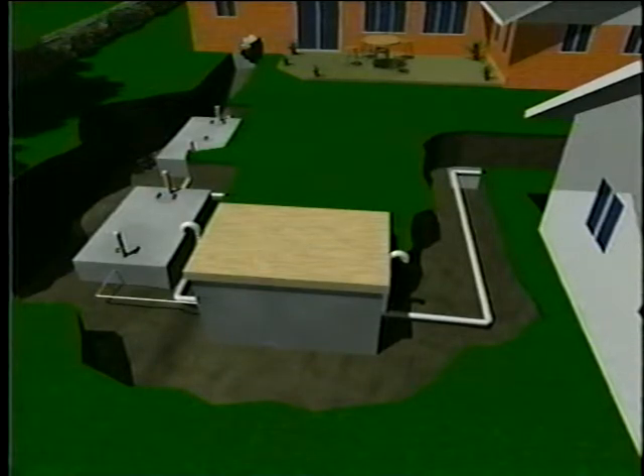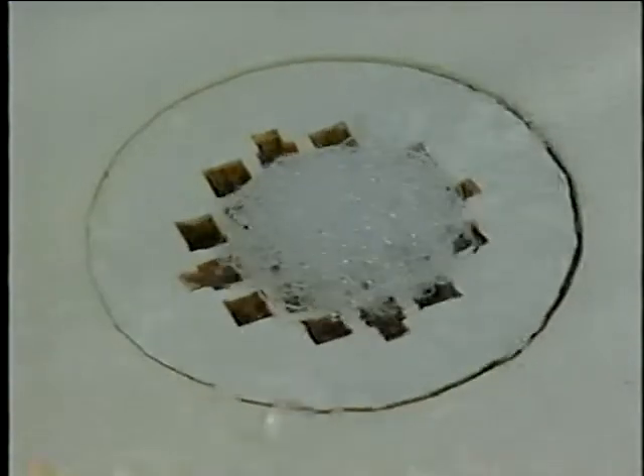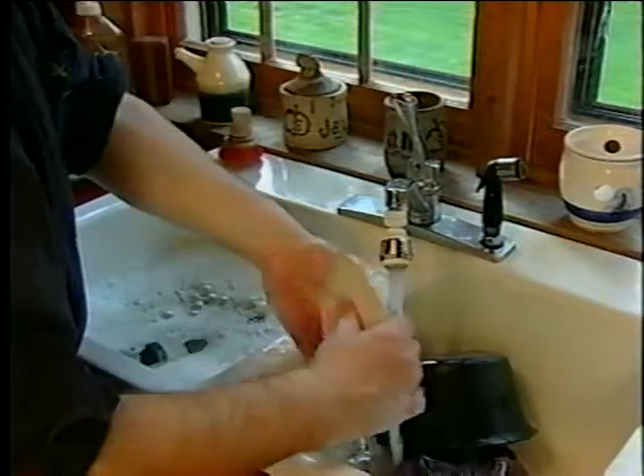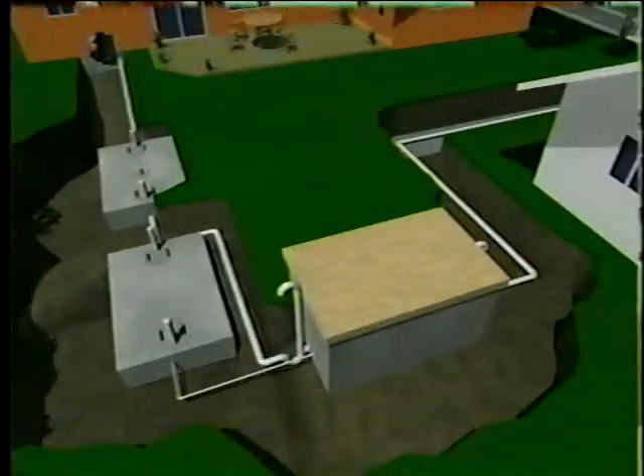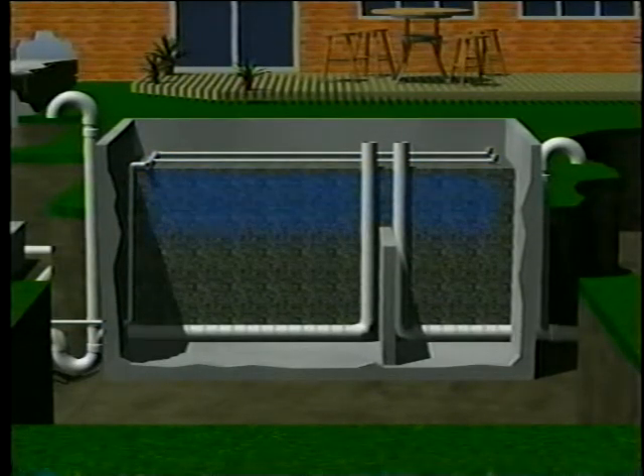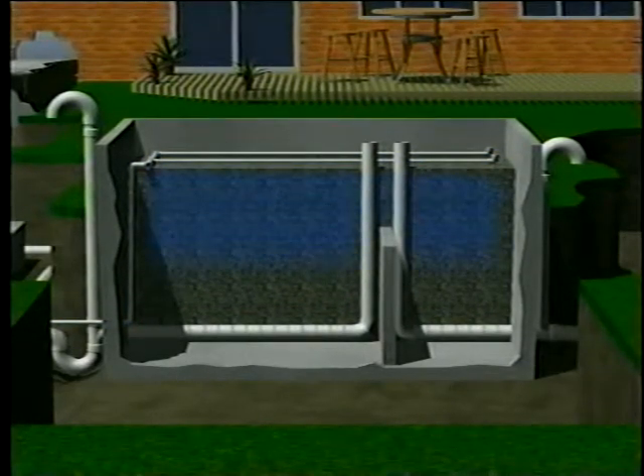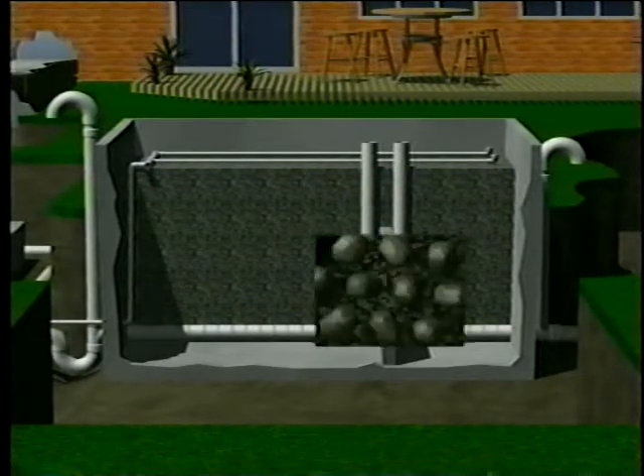During a 24-hour period, the amount of wastewater entering the septic system fluctuates. Peak flow periods are typically in the mornings, evenings, and weekends when families are taking showers, doing laundry, and washing dishes. At night when people are sleeping and during the day while people are at work and school, there is less flow to the septic system. With a recirculating filter, one of the goals is to manage these variable flows so that the effluent is pumped to the recirculating filter evenly throughout the day. You don't want to oversaturate or flood the filter. Instead, you want to give it a dose, let it soak in, then give it another dose. Small volume doses allow the effluent to move slowly through the sand or shale particles with plenty of time for natural bacterial reduction to take place. By contrast, if you were to flood the system, the effluent would percolate so rapidly through the sand that there wouldn't be enough contact time for adequate treatment.